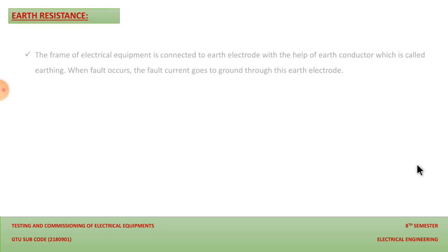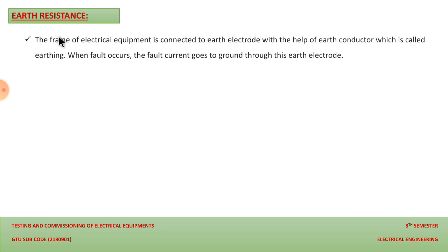So let us discuss what is actually the earth resistance. So the frame of the electrical equipment is connected to the earth electrode with the help of an earth conductor. That we have already discussed, that the frame of any equipment which is connected with the GI wire is called the earthing. And when any type of fault occurs, the fault current goes to the ground through this earth electrode. So this is the necessary point that should be fulfilled with the help of the earth electrode, because whenever such type of fault occurs, the charges must be transferred through the earth electrode, not through the human body.